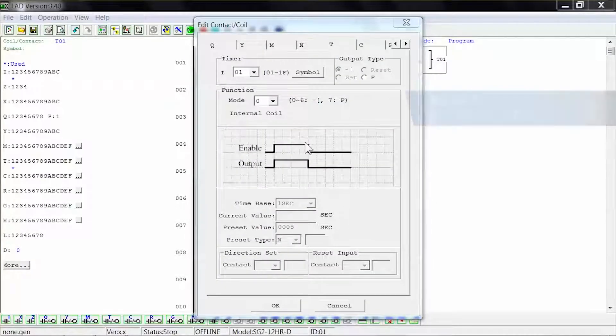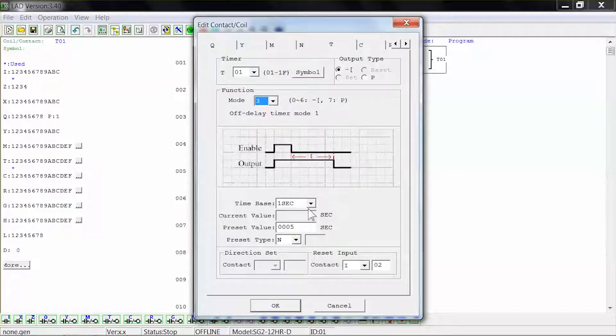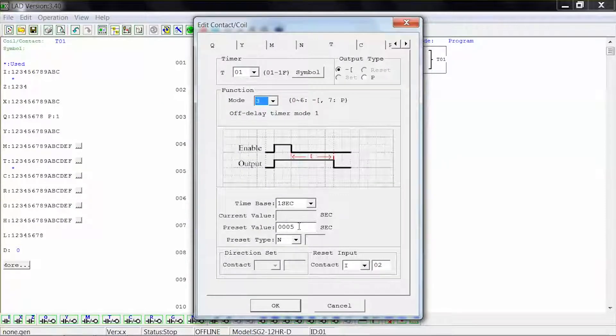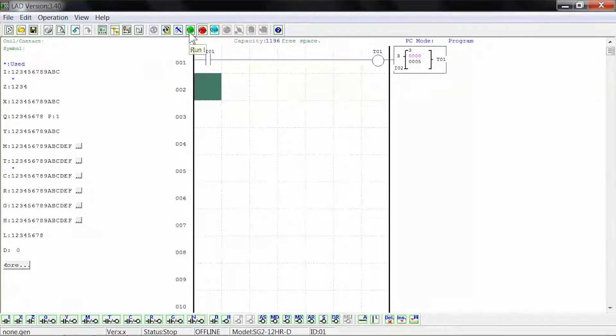For this example, we will select mode 3, which is an off-delay timer version 1. We will select 1 second for our time base and 5 seconds for our preset value, shown as 0005. We will select N for our preset type, which stands for numeric constant. And for our reset input, we will select contact I02. Click OK to close the window and click run to start the simulation.